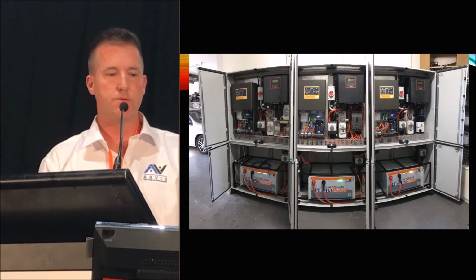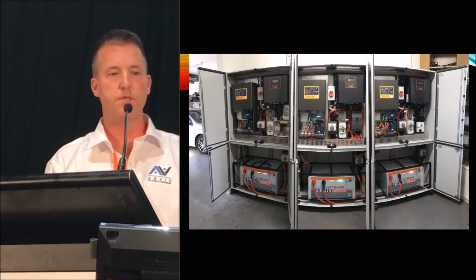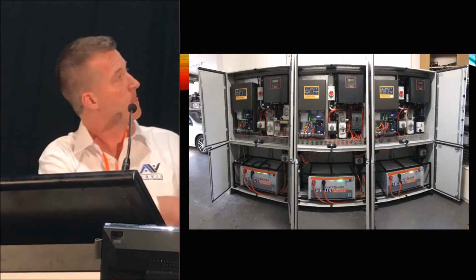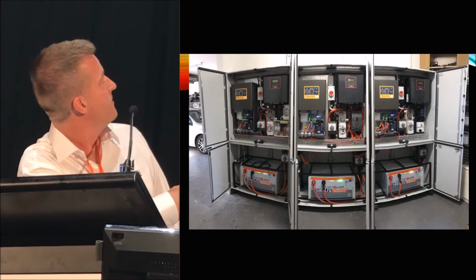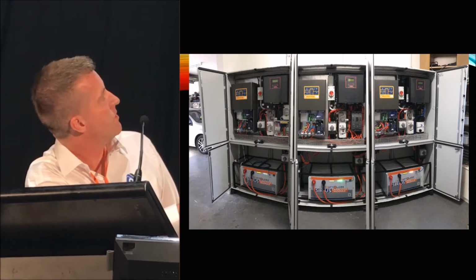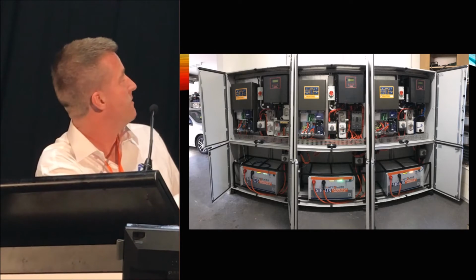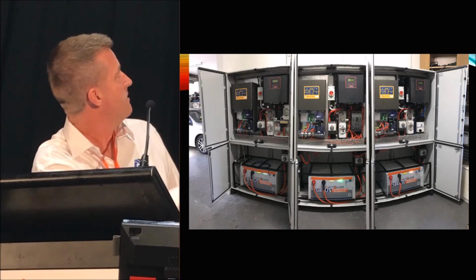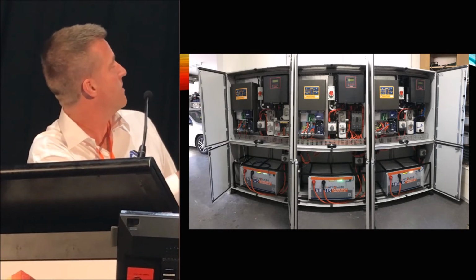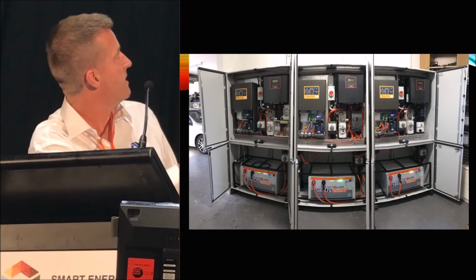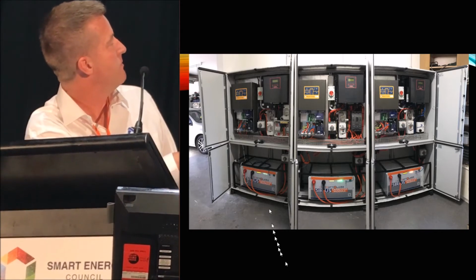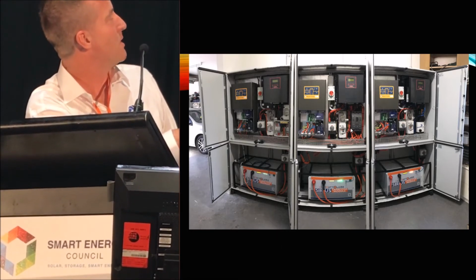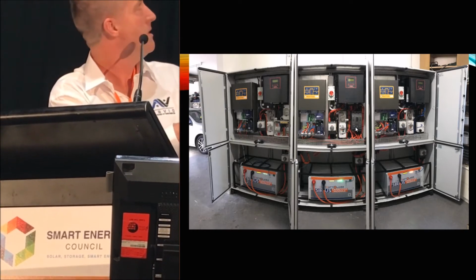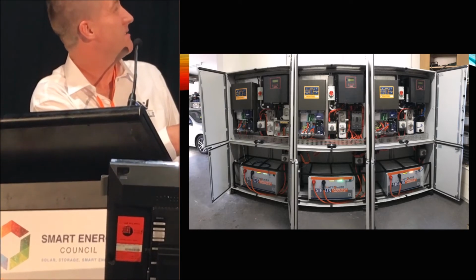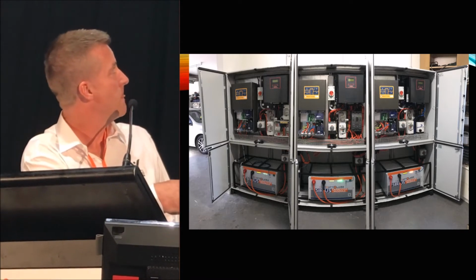That's the cabinet there installed. So 3 modules there, fully monitored. You've got here 3 SP Pro inverters, 3 charge controllers, 15 kilowatts of solar panels on the roof. Got here a switchboard which brings all this stuff together. We call this the AC cabinet, where we've put all the AC together. We call this a DC cabinet, where we've got a big mother of a DC circuit breaker here that's 630 amps with a fault current rating of about 80 kA, I think it is.